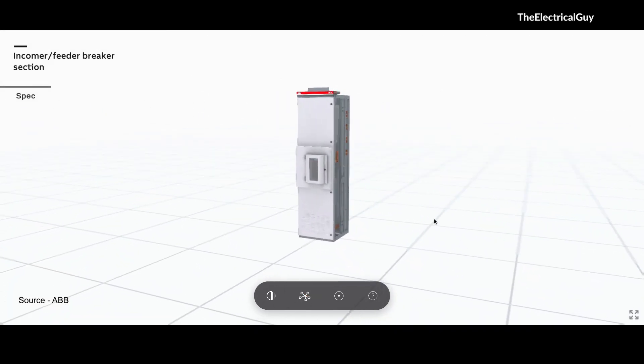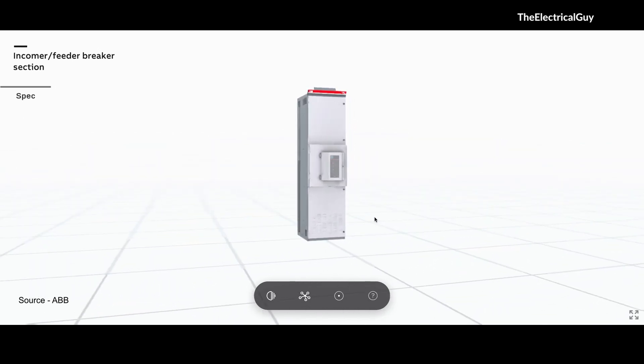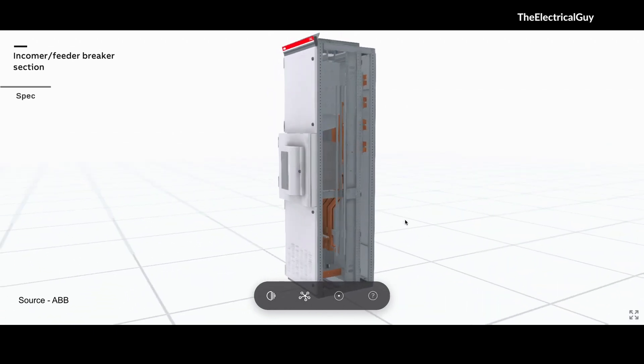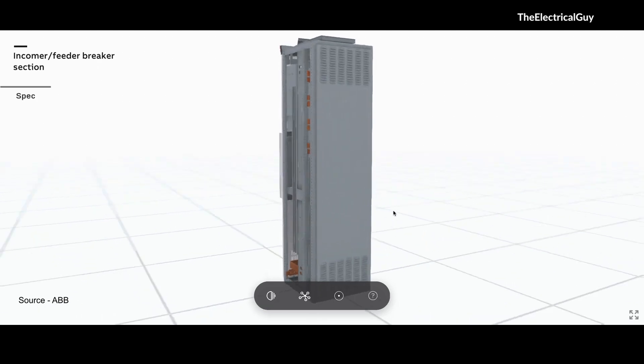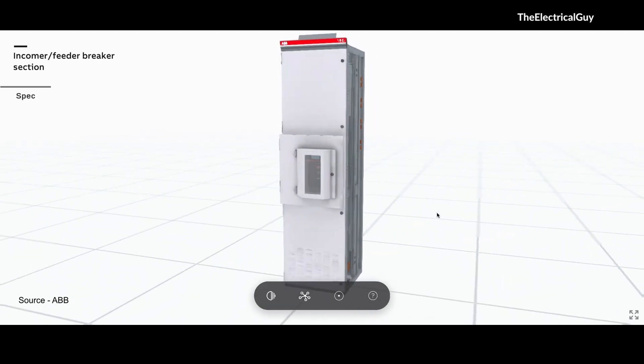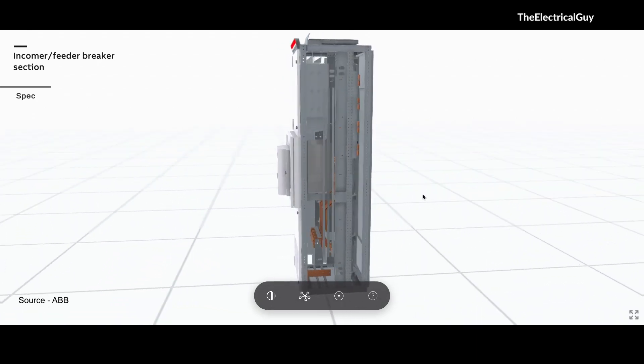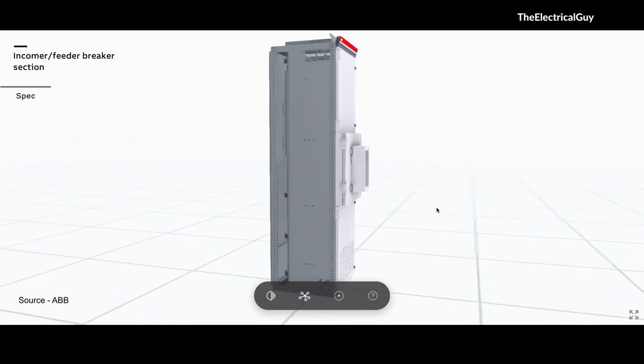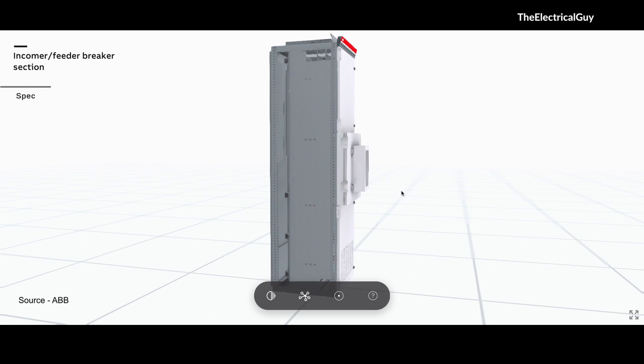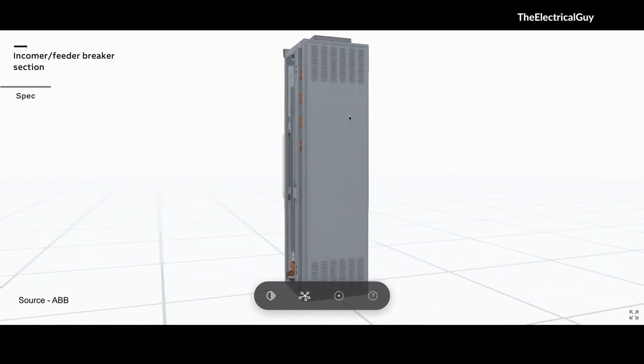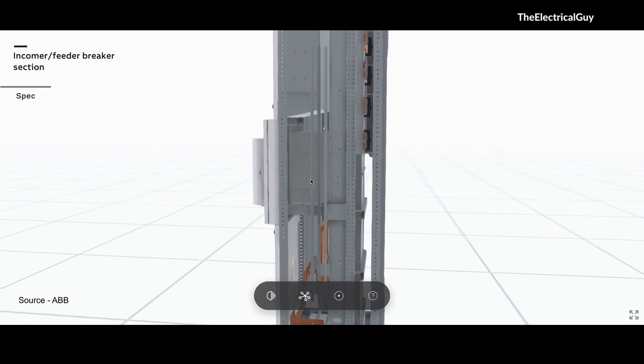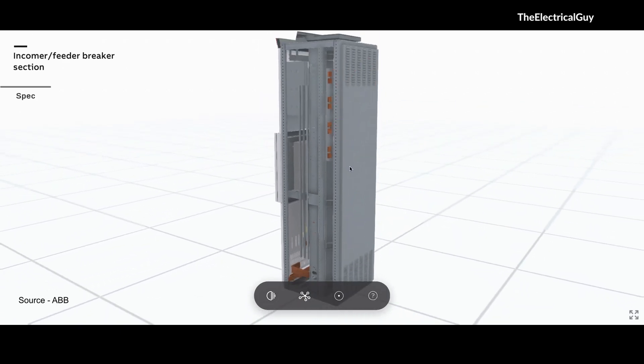What you can see on your screen is a simple incomer feeder breaker panel. This panel can be used as an incomer panel or as a feeder panel. A feeder panel is one which supplies power to some other substation or a different load, while an incomer panel accepts the incoming supply. This is the front side with a door, the left side is covered by a metal sheet, the back portion is also covered with ventilation ports, and the right side is open — meaning it is extensible and you can add more panels to the right.